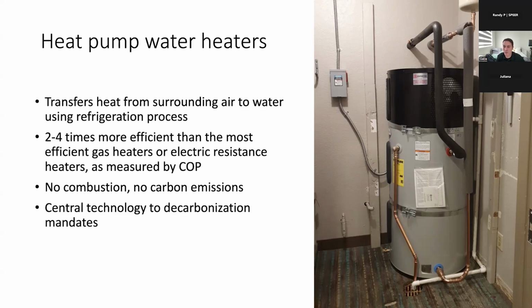Because even the most efficient tankless water heater might get 95, 96% thermal efficiency, whereas with a heat pump water heater, you can achieve up to 400% thermal efficiency. So the efficiency is off the charts. For every one unit of energy, you get three to four units of hot water output. It's really great in areas where they work. There's no combustion, there are no carbon emissions, and it's a central technology to decarbonization mandates.